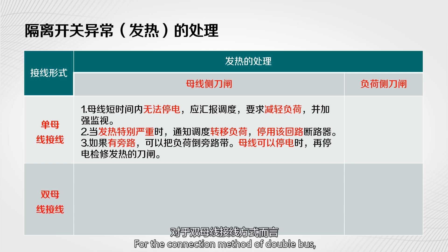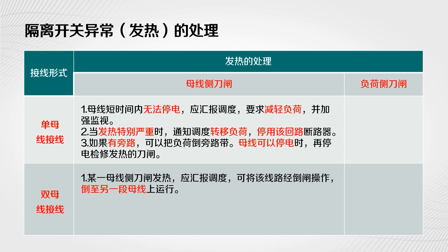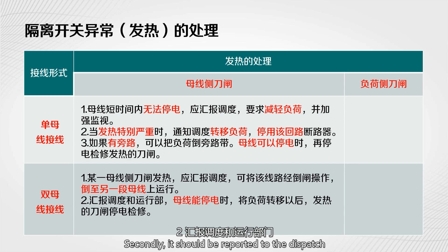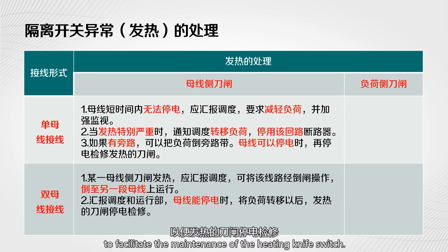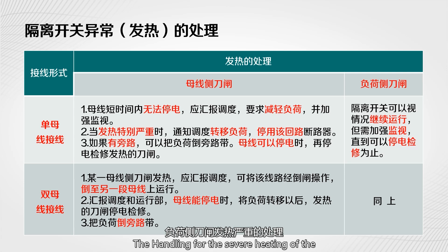For the double bus connection method: First, if the knife switch of a certain bus bar heats up, report to the dispatch department and switch the line to another section of bus for operation. Second, report to the dispatch and operation departments so that when the bus can be powered off, the load is transferred to facilitate maintenance of the heating knife switch. Third, switch the load to the bypass belt.